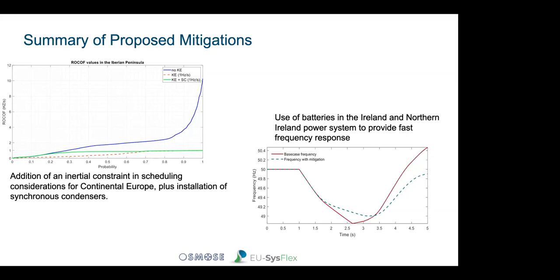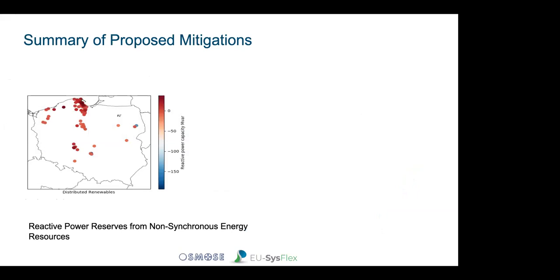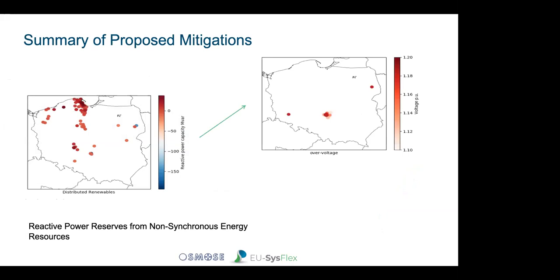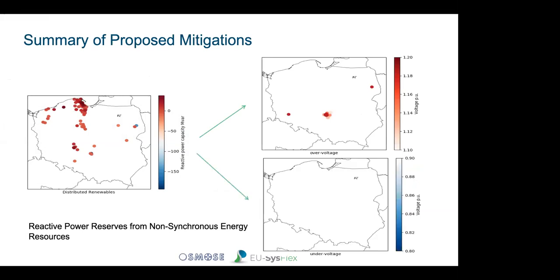Finally, on the next slide, the provision of reactive support from non-conventional resources, in this case wind generation, was simulated and illustrates how the voltage stability issues in Poland, for both over- and under-voltage issues, can be mitigated. If you click forward, you can see a significant decrease in the number of over-voltage issues, and essentially all of the under-voltage issues have been resolved.